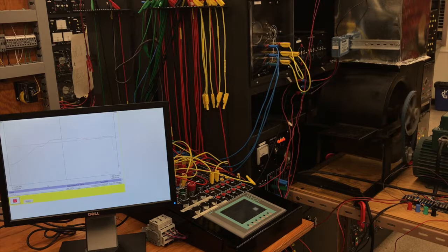Now we're changing to a different preset, so the system will try and bring the air temp down to the new lower level. It increases the fan speed to bleed off the heat. At the same time, it will shut off the heater. You can see the trend line starting to drop to our new preset. And as we get closer, the fan will slow down.